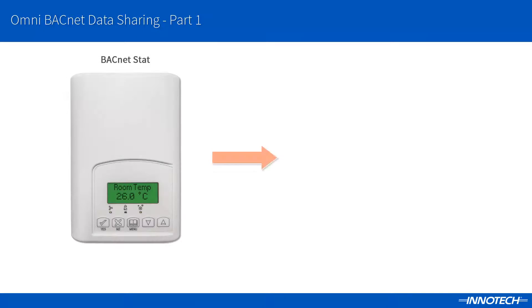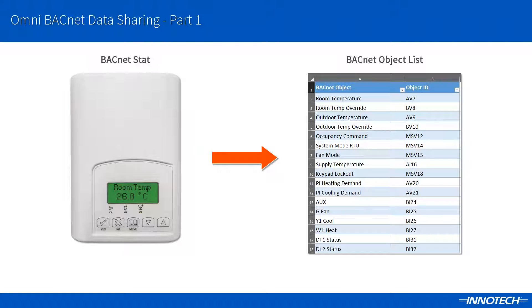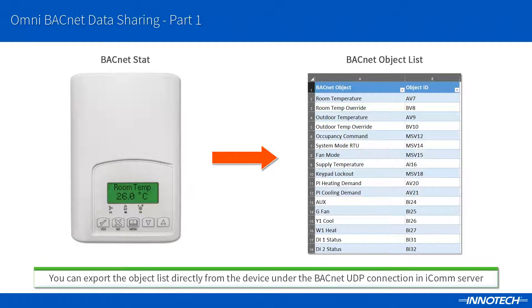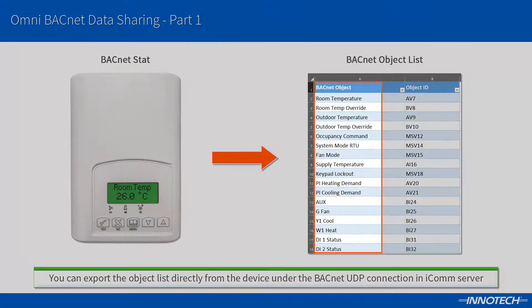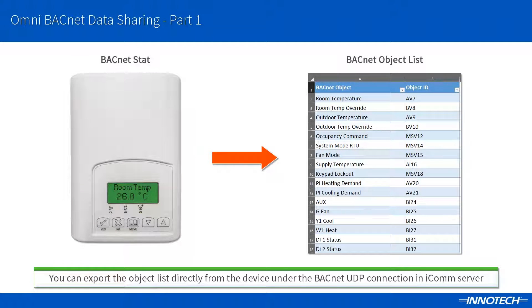It is important to obtain the BACnet object list for the device that you wish to share data with. Once the device can be seen in the ICOM Communication Server BACnet connection, you can export the device object list — we will see this in part 2 of this series. In this example, I have extracted the BACnet object list and have a portion of the resulting CSV file. From this I can see the object name and its associated object ID. Note that some devices may not provide the full object names and this is entirely dependent on the manufacturer; in that case you would need to contact the provider for more information.